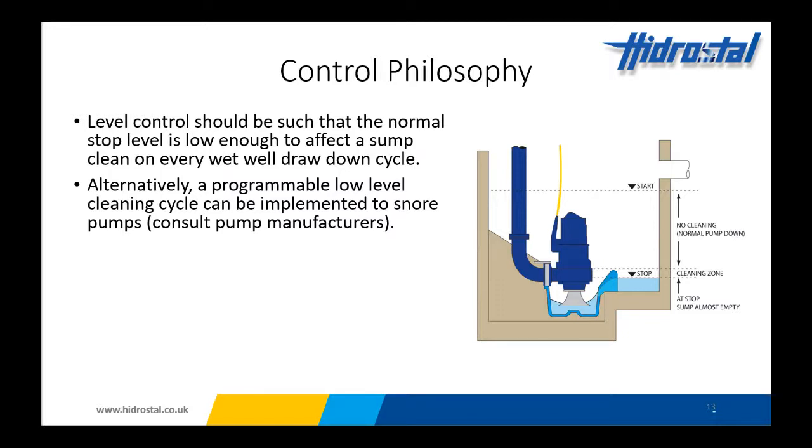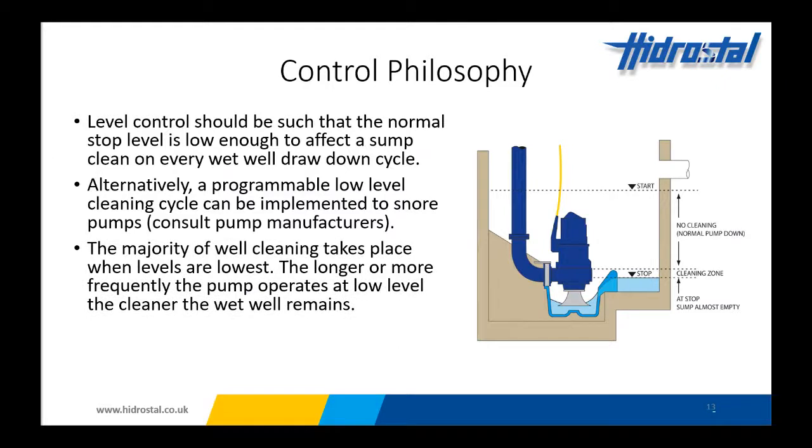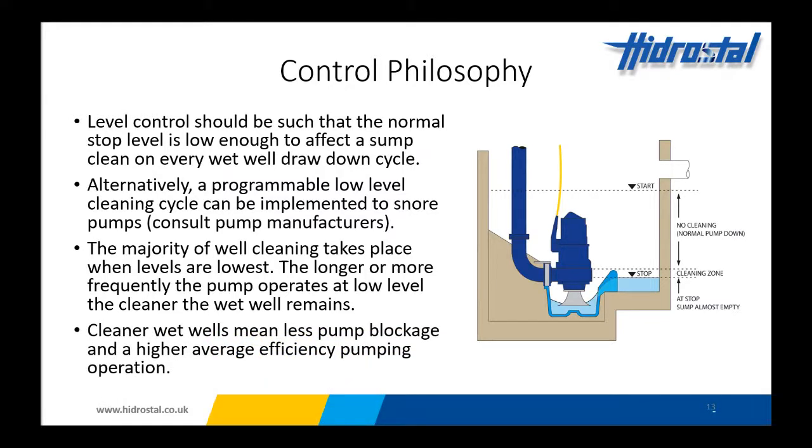Different manufacturers have different recommendations, so it's worth speaking to the manufacturer of the equipment, of the pump. But you must remember that the majority of well cleaning does take place at the lowest levels. And whilst this means higher static head, higher energy, the benefits of keeping the station clean, keeping the pumps from clogging, can often outweigh some little bit of energy loss sometimes. So cleaner wet wells mean less pump blockage, higher average efficiency pumping operation. So something to definitely try to get right.